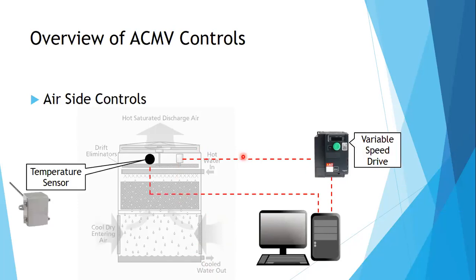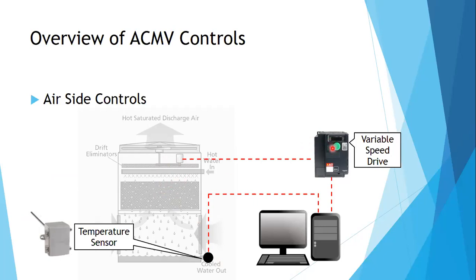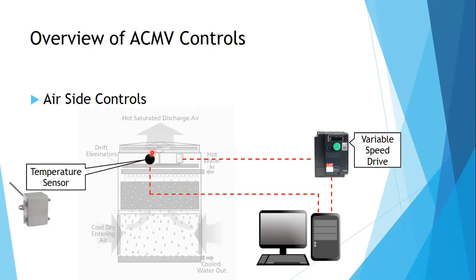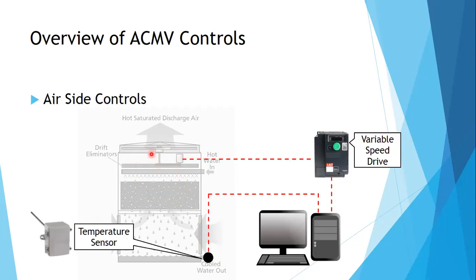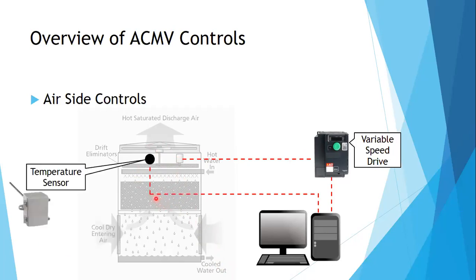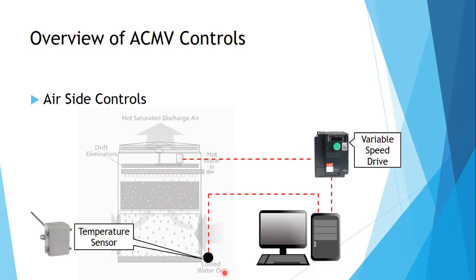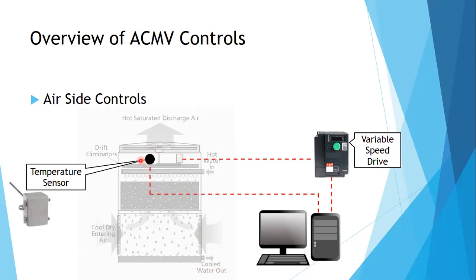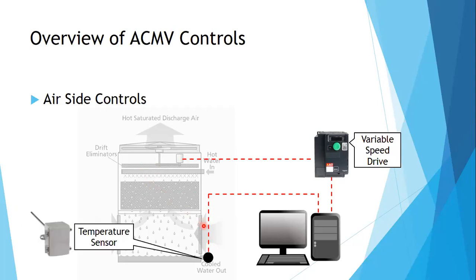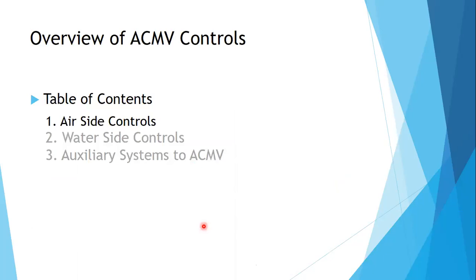So that's another way. You get the same effect if you monitor your air or your water, provided that you're controlling the same equipment, the cooling tower fan. So there's more than one way, no? Some people will go with the temperature sensor on the air, or some people will go with the temperature sensor on the water. It doesn't matter, as long as you write the correct logic. But just make sure that you're measuring the outlet side. Air out and water out. So that's our air side controls.